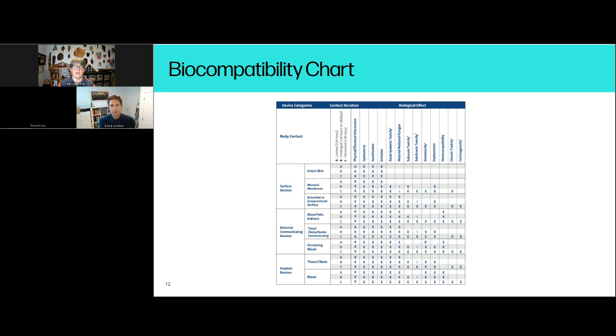Some people will actually do chemical characterization with a test lab, which means that they pull the chemicals off of the finished good and then evaluate those chemicals to determine whether or not there are any concerns with whatever chemicals are remaining. That has to then be reviewed and approved by a toxicologist. It's probably worth your time and your money to have that done as a starting point, because that feeds very well into justifying not having to do all of those tests.